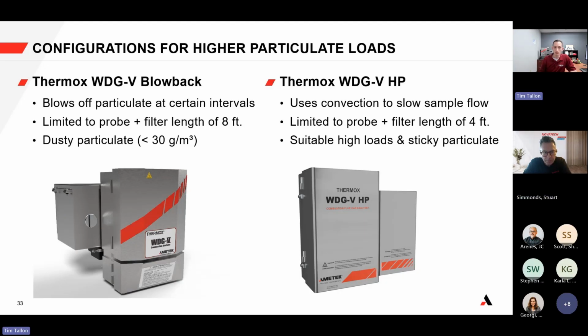For the HP2 and the WDG-V HP, without having an aspirator, there's a much slower flow, and that slower flow allows it to draw a sample without creating massive suction. That's where we found the sweet spot - above that 30 grams per meter cubed and much higher levels. We've even seen the HP2, the predecessor of the WDG-V HP, handle saturated water streams after a scrubber - high particulate load, sticky particulate, and even saturated streams in a number of cases.